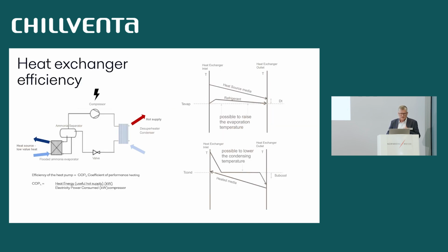So how are we working with efficiency on these heat exchangers? With plate heat exchangers, there is a possibility to increase the efficiency. The COP is how much heating energy we produce over the input of power to our system. If we can increase the evaporation temperature by 1 K, we can sometimes improve efficiency by between 3 and 6%. And if we can lower the condensing temperature, we can increase efficiency by up to 3%. As you can see here, we have solutions with condensers where, in one heat exchanger, we can heat the secondary side above the condensing temperature using the superheat in a combined solution. These are things we are doing to improve efficiency and compactness.